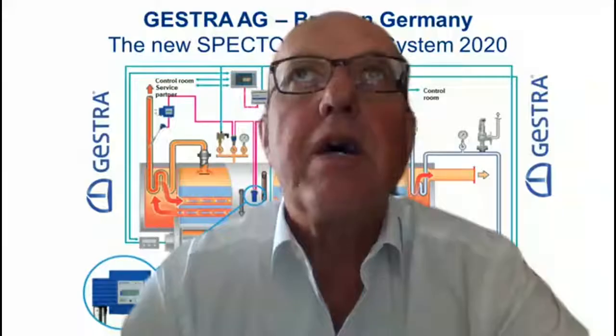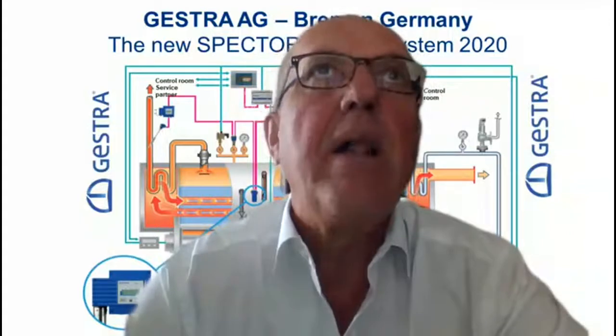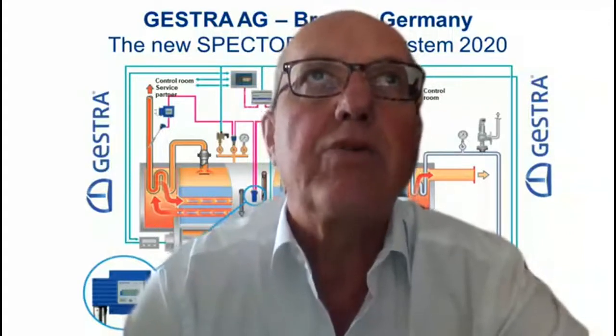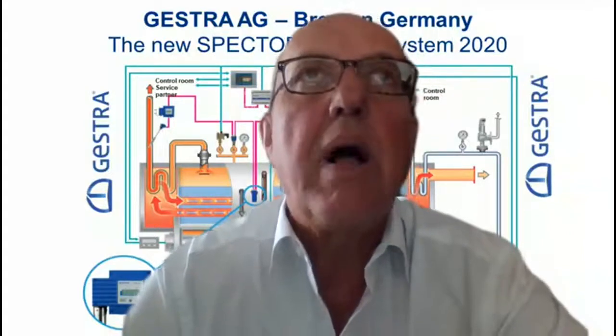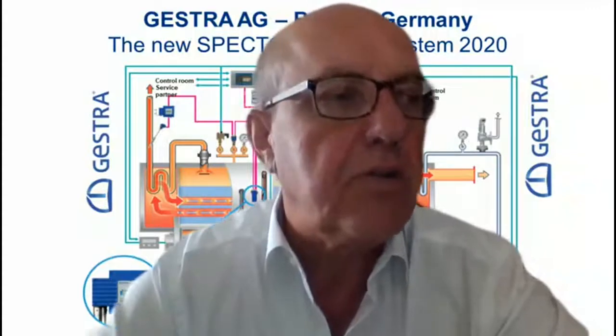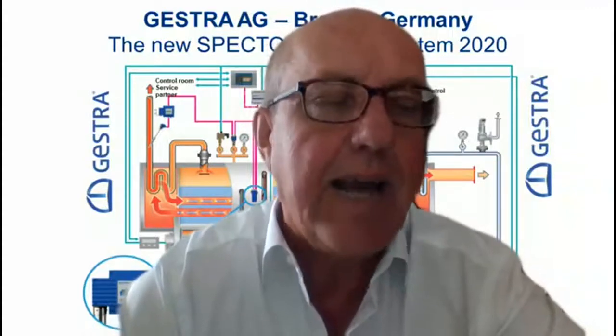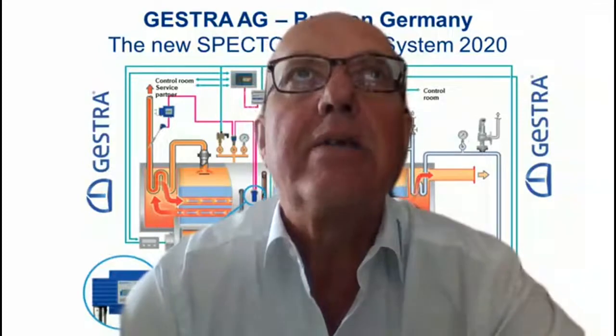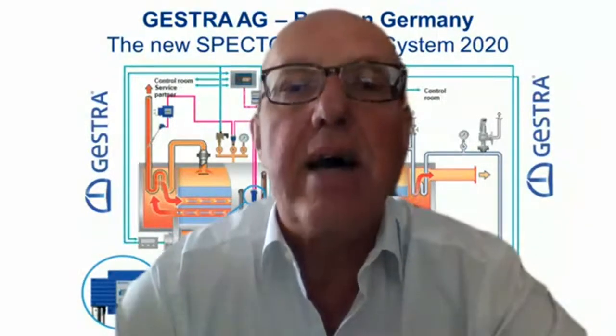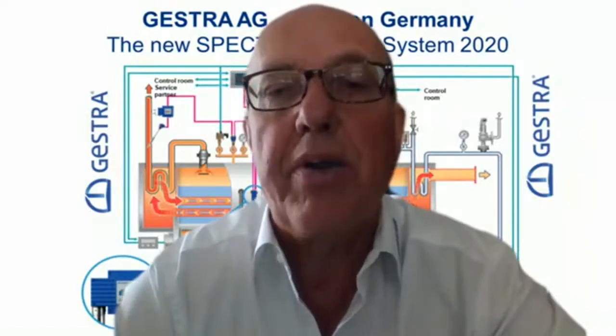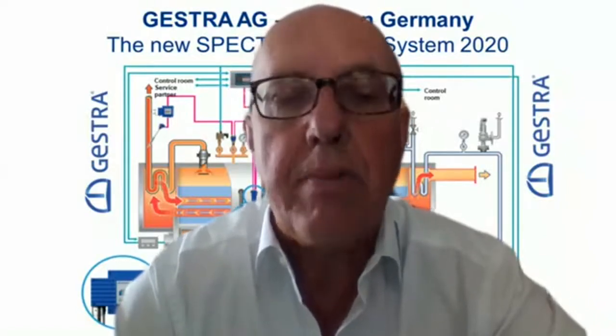I just saw that there is a question: what is the normal troubleshooting for a thermostatic trap and ball float trap? Troubleshooting on a thermostatic steam trap means that you make an annual test with an ultrasonic device. What we can do continuously is to install a sight glass, which is able to show that there is a leakage of steam or a backing up of condensate. That is in our normal product program.